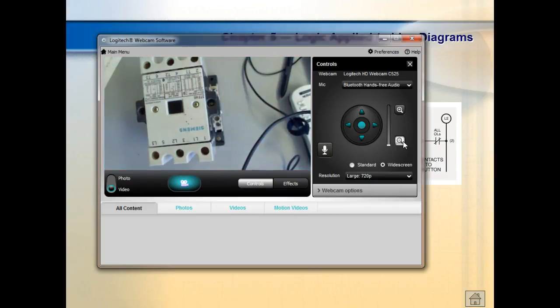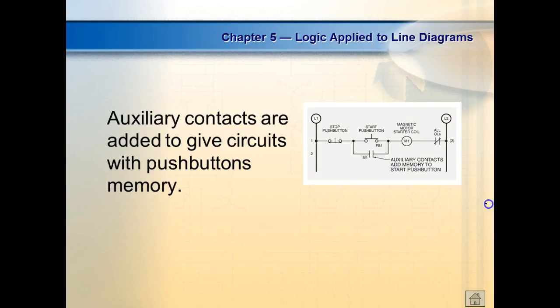Are you okay? So auxiliary contacts allow us to have a contactor or a motor starter. These contacts are for the power circuit, then your auxiliary contacts will be part of the control circuit. Okay, y'all understand that? So here we got a motor starter, magnetic motor starter. So that means somewhere in there is an overload, so it's probably three-phase, we have a power circuit. So the three-phase motors are going to be out here. This is called M1, so these right here would be labeled M1. By the way, let me draw a little more too.